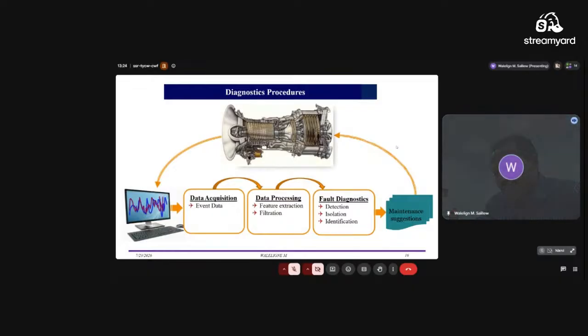The detection module is to detect whether there is a fault or not. It's responsible only for detecting if a fault is happening or not. The second package, if the first package detects that there's a fault, is to isolate the fault. If a fault is happening, what kind of fault is happening in the system and which component is affected? So it's isolating the type of fault and the component affected by the fault. And the third one is identification, which means, okay, a fault is happening. Let's say fouling happened in the system, and how much the flow capacity is reduced, how much the efficiency is reduced. So it's quantifying the magnitude of the fault.